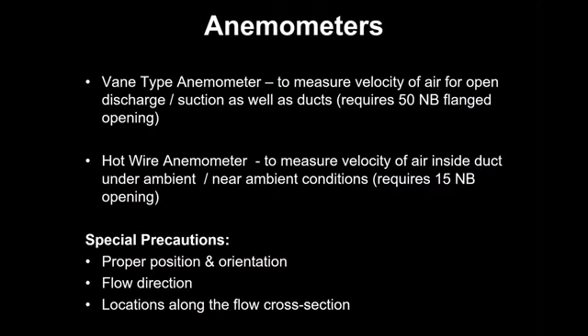Now, the anemometer is more important. There are basically three types of instruments available for measuring the flow of liquid, air and gases. The commonly used one is the vane type anemometer. This is to measure the velocity of air, but mostly it needs at least one side to be open. Either discharge or suction has to be open to atmosphere. Otherwise, you need a 50 NB or maybe now 25 NB flange connection through which it can be inserted. But inserting it means some air is going in, some air is coming out. That is not a very good thing. So the vane type anemometer is normally used on the open side of the suction or discharge.